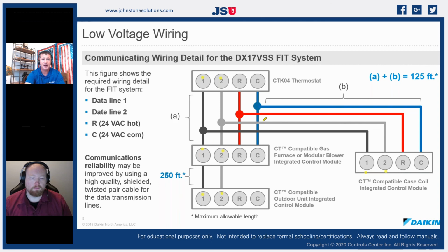We also need to verify what that voltage is. So we need to check from common to 2 to see if we have around 2.2, and common to 1 to see if we have around 2.8. Say I had at the thermostat 2.8 on number 1 and 2.2 on number 2. That would give me my 0.6 volts. And I had the same thing at my indoor unit and at my coil, but I got to the outdoor unit and maybe I only had 2.5 and 1.9. Well, that's still 0.6 volts, right? But it's the wrong 0.6 volts. We've had some type of voltage drop. So even though we had the same 0.6 bias between our network, if we had a voltage drop, that means we had something wrong on that control wire.